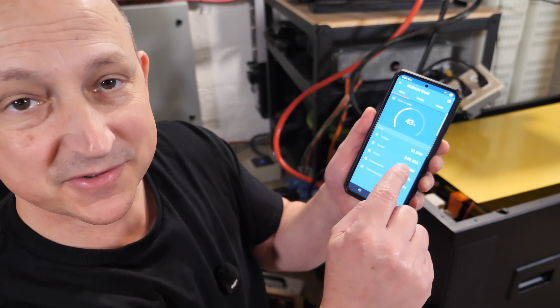Boom shunt saying 44% state of charge, still drawing 12,000 watts according to this, and we've consumed 355 amp hours, or 18.3 kilowatt hours. Looking here, we're actually drawing around 250 amps, so I'm going to lower it down a little, because I think inside the BMS settings it might be set for 250 amps.